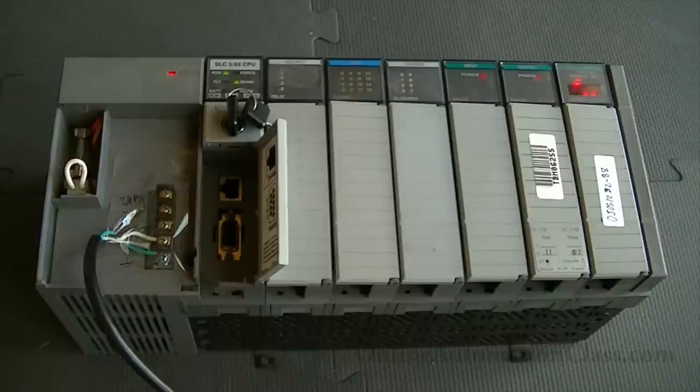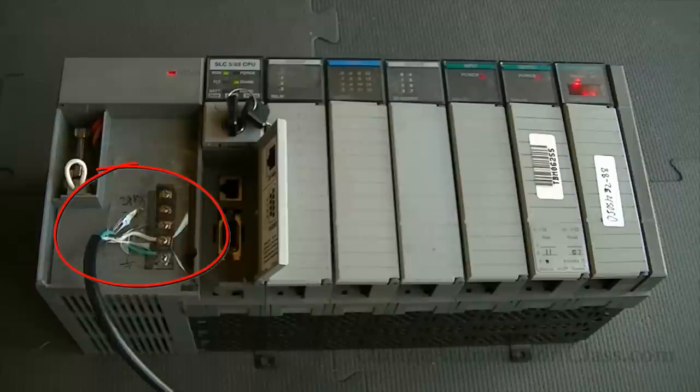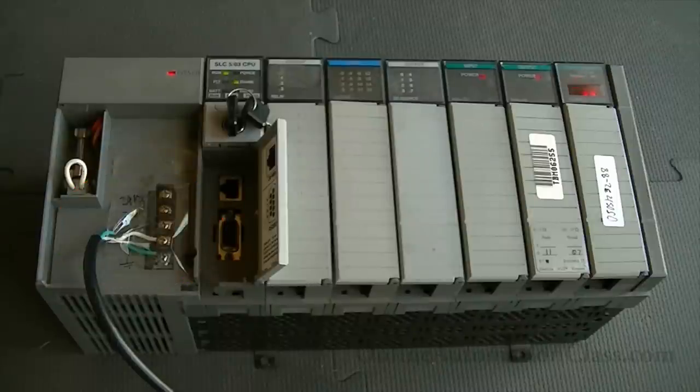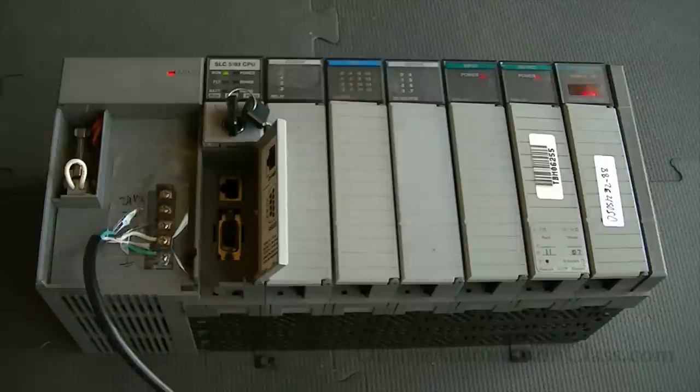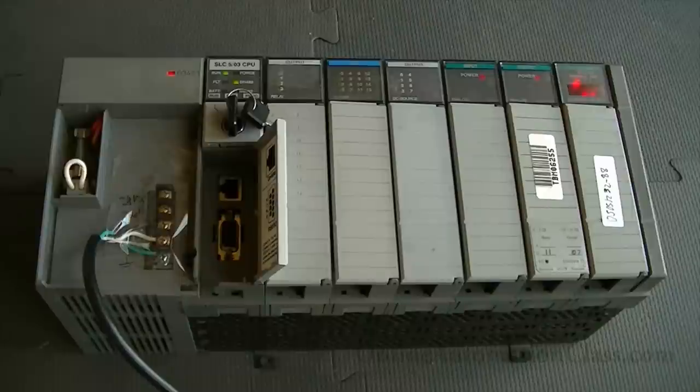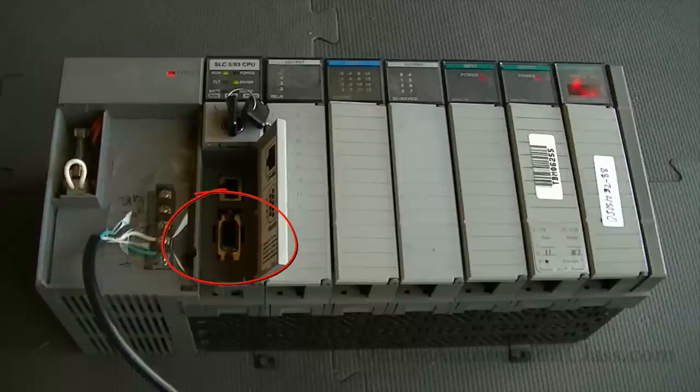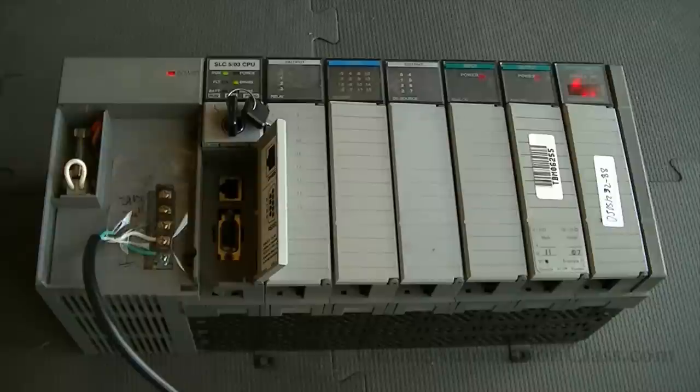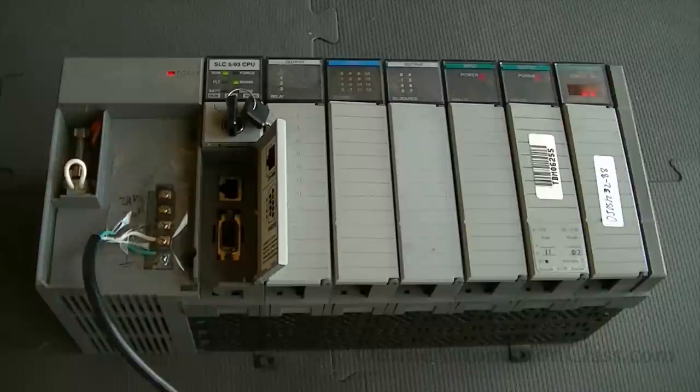Before using RSLinx to configure and establish the communication link, the SLC 500 PLC is powered and physically connected to the PC with a communication cable. For the 1747L531 processor, a null-modem serial cable is required. One end of the null-modem serial cable is connected to the RS-232 port of the processor and the other end to a USB to RS-232 adapter. The PC running the RSLinx program does not have a built-in RS-232 serial port, so a USB to RS-232 converter is used.